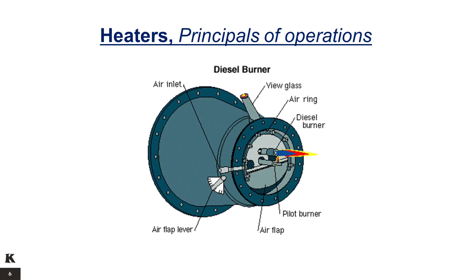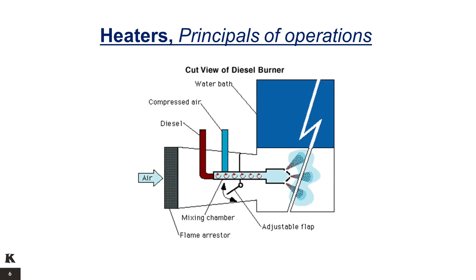An air-driven hydromechanical gear pump will pump a maximum of 55 barrels per day in order to fire the heater. There is no integral fuel tank and typically the pump sits on top of a drum full of diesel. The flow rate of the diesel supplied to the burner is controlled by adjustment of the air regulator on the pump unit.